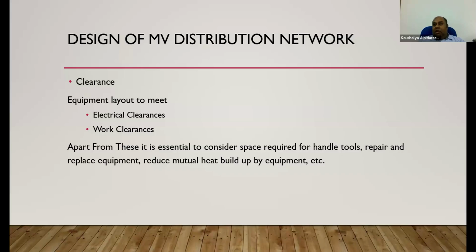How is a person going to handle this job, and what extra space is required during a repair, or moving a, let's say, a transformer out for a repair, or you are replacing a transformer? What is the most suitable path? What are the clearances you need? Those are, of course, physical clearances to take out the transformer. If you can't lift it or push it, you may need at least a forklift to lift it up and take it out. So you need to have adequate space for those.